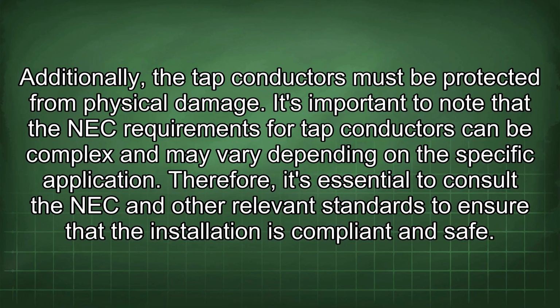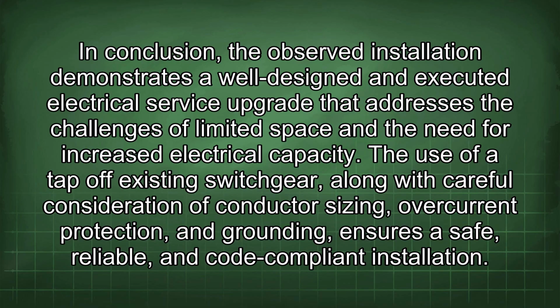It's important to note that the NEC requirements for tap conductors can be complex and may vary depending on the specific application. Therefore, it's essential to consult the NEC and other relevant standards to ensure that the installation is compliant and safe. In conclusion, the observed installation demonstrates a well-designed and executed electrical service upgrade that addresses the challenges of limited space and the need for increased electrical capacity. The use of a tap-off existing switchgear, along with careful consideration of conductor sizing, overcurrent protection, and grounding, ensures a safe, reliable, and code-compliant installation.